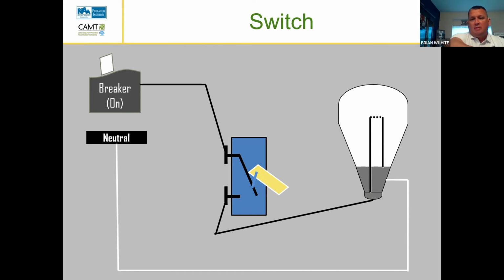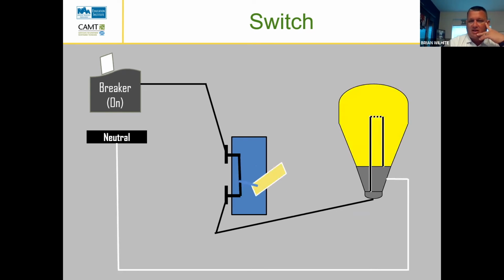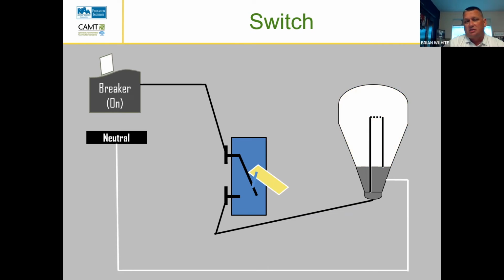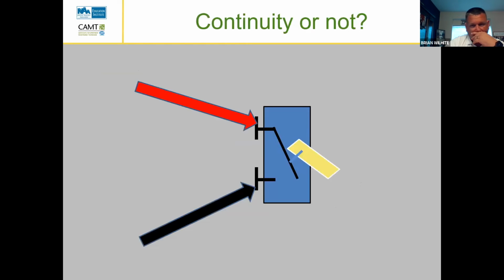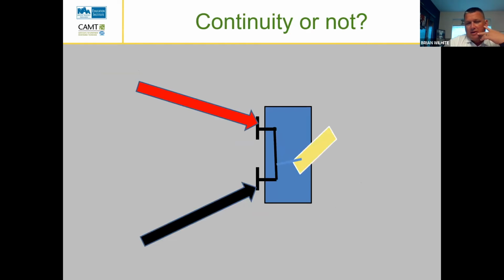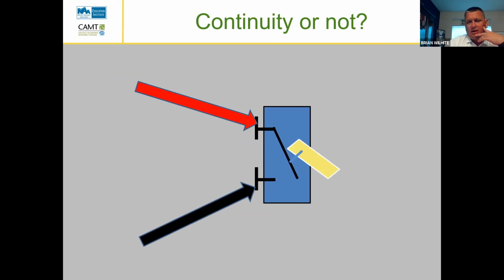At this point, my line coming from my breaker is my 120 volts, but my switch is open. So the bottom part of my switch right now is nothing. It's neutral. So I should have 120 volts. We'll get to that in another second here. So if I turn that switch on, look how that lights up. See, that's pretty high tech. So when I close that switch or open that switch, it feeds me power. What can I test? What can I use to test this switch to tell me if it's bad or good?